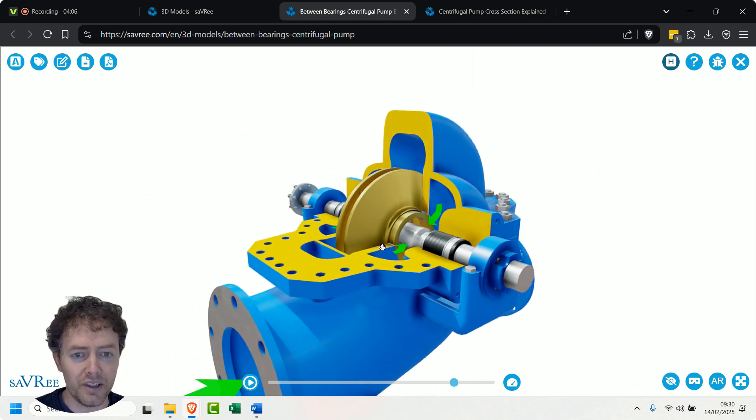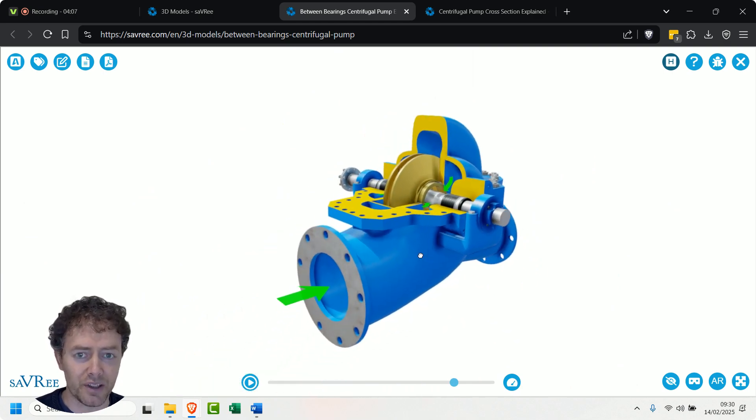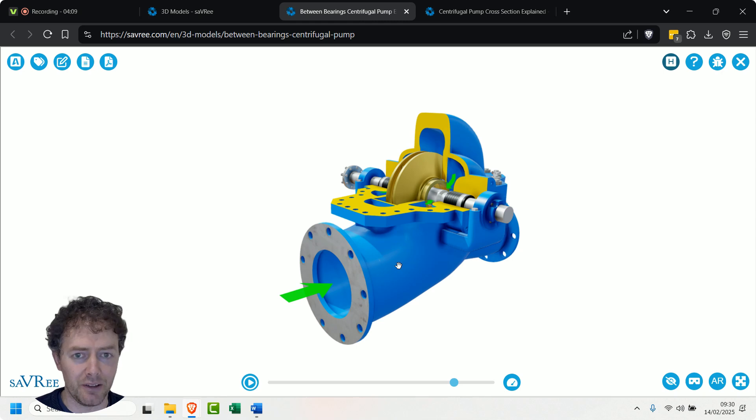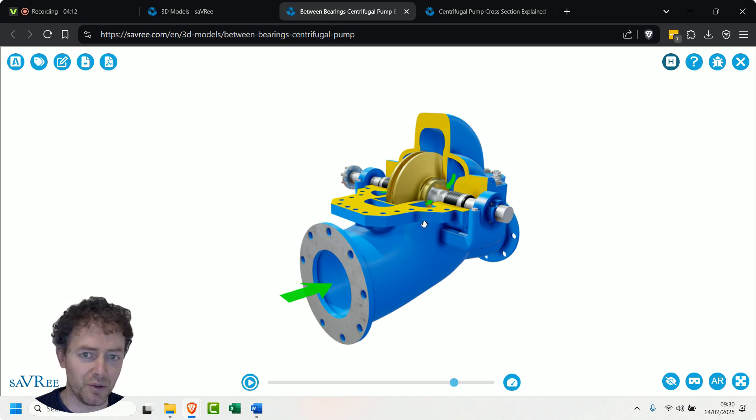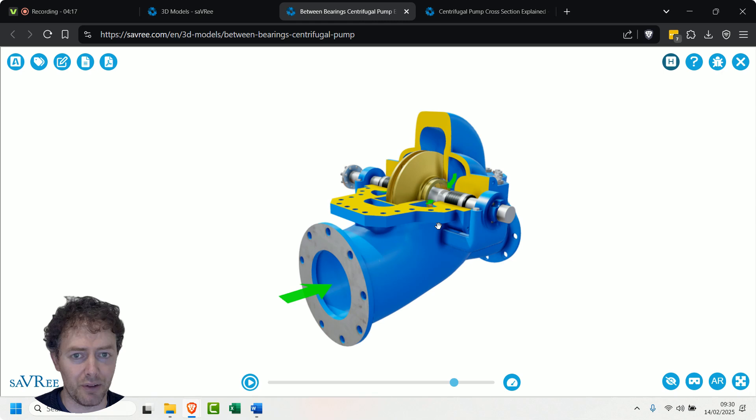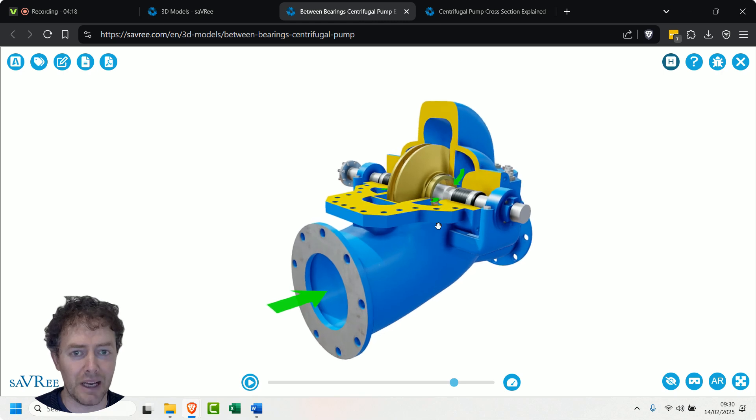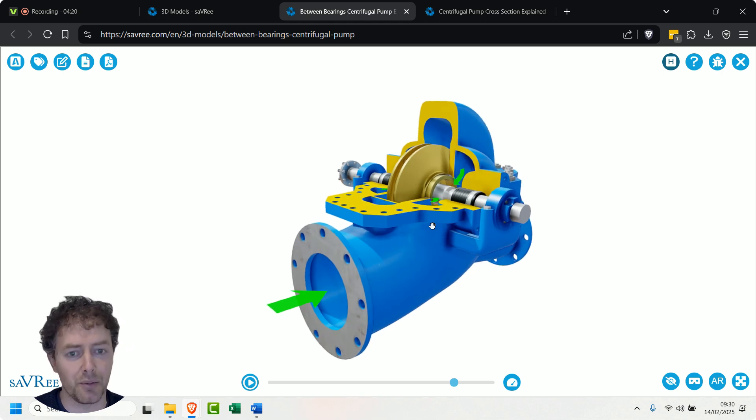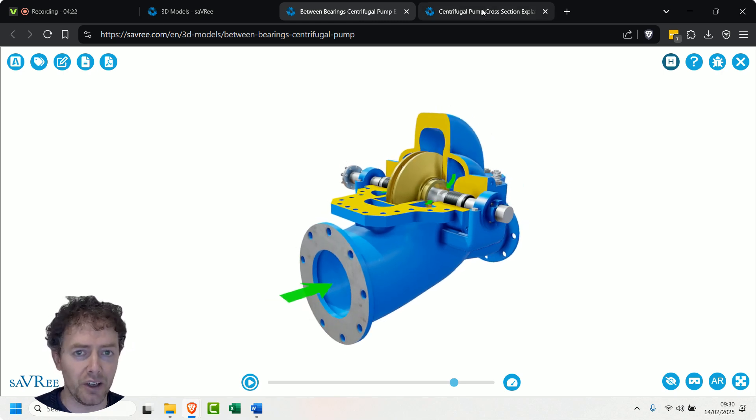So it's like combining two overhung pumps into one. Why would we do this? We do it because the pump's bigger, the impeller is bigger, there are more forces that you need to balance, and so you install the impeller in between two bearings in order that we can have a larger impeller and balance some of that vibration and some of those forces a little bit better.